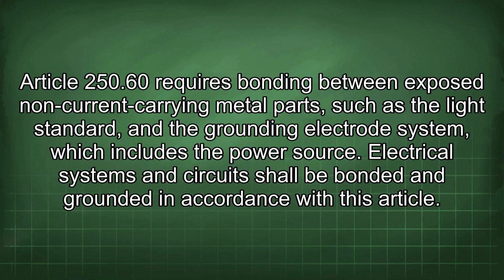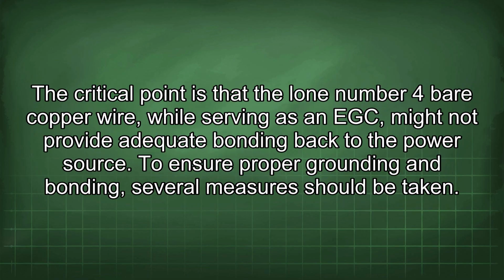Article 250.60 requires bonding between exposed non-current carrying metal parts, such as the light standard, and the grounding electrode system, which includes the power source. Electrical systems and circuits shall be bonded and grounded in accordance with this article. The critical point is that the lone number 4 bare copper wire, while serving as an EGC, might not provide adequate bonding back to the power source.